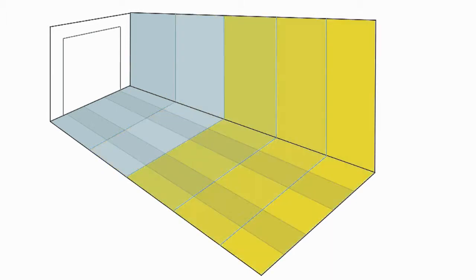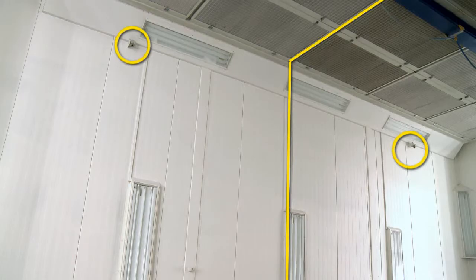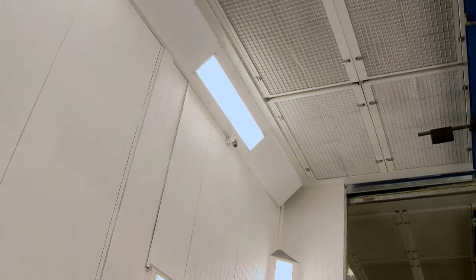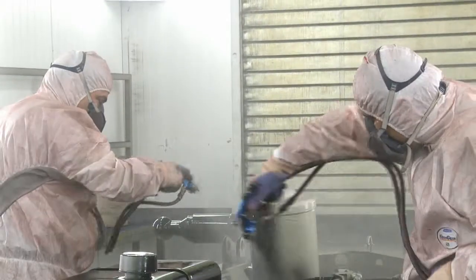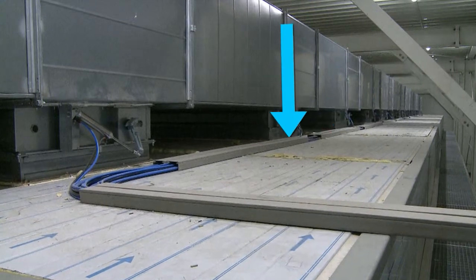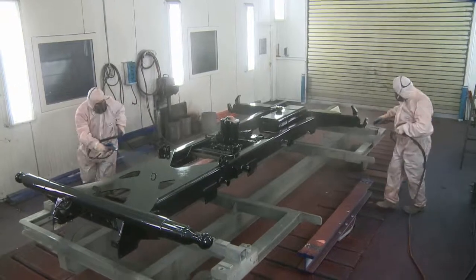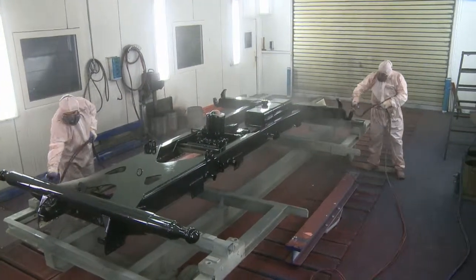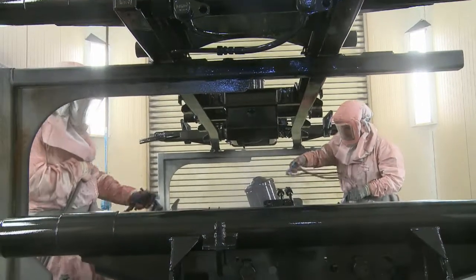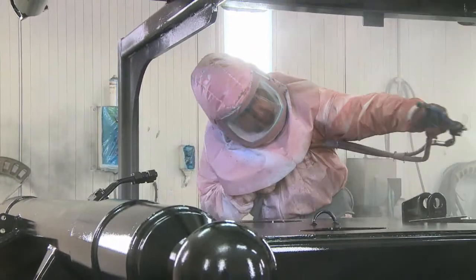Precisely calibrated motion sensors transmit the technician's current position to the control system. The system regulates where fresh air inlets are opened in the filter sealing and which of the corresponding floor flaps are opened to target and extract the overspray. Compared to conventional ventilation systems, which must turn over 84,000 cubic meters an hour, the sectional system shown here makes do with only 50,000 cubic meters an hour.